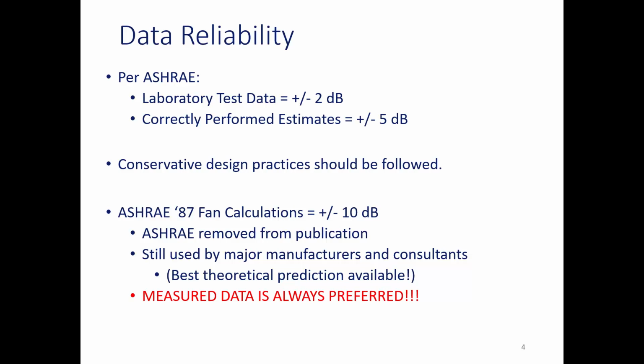The third best option is if you really don't have anything to go off of - and this happens quite often - then you can turn to predictions like this. Lots of manufacturers use this. Sometimes I'll see the sound power data a manufacturer provides for their equipment, and right there in the small print they say they used the ASHRAE 87 calculations. So they're using it, I use it, it's useful. A lot of consultants use it just because there's not really anything better. But there is a good amount of error, so you want to be conservative when designing using this.